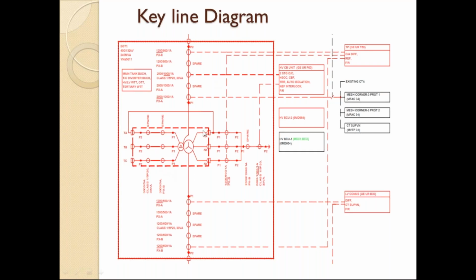Similarly, there is a neutral and a tertiary winding. Normally in an auto transformer there is the HV side, the LV side, a neutral, and a tertiary side. This is for the Taunton project, one of the projects, and we will represent it like this. This is the LV side. This transformer is 400 kV, SGT1 400 by 132 kV. This is the HV side of the 400 kV substation, and this is the 132 kV substation. So what protection will come for the 132 kV?